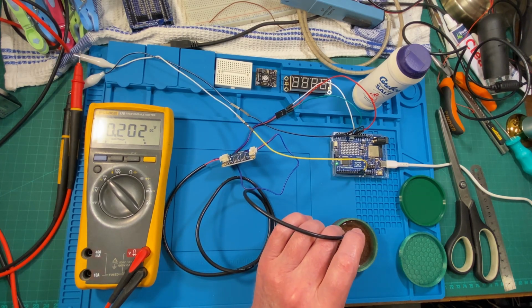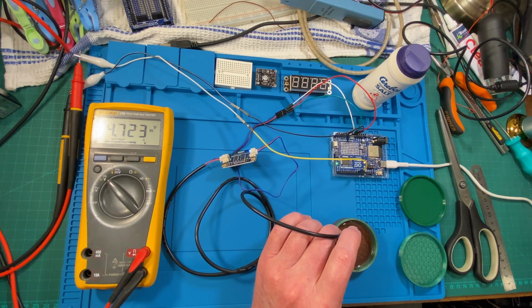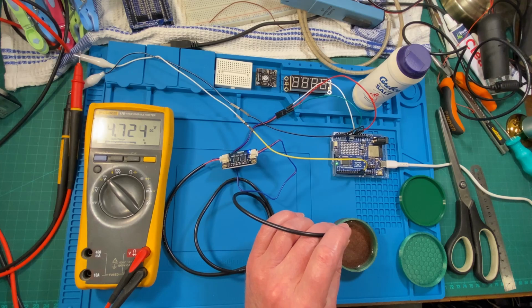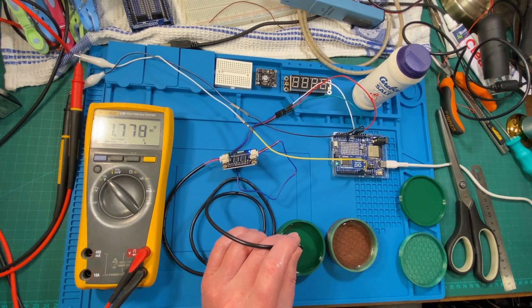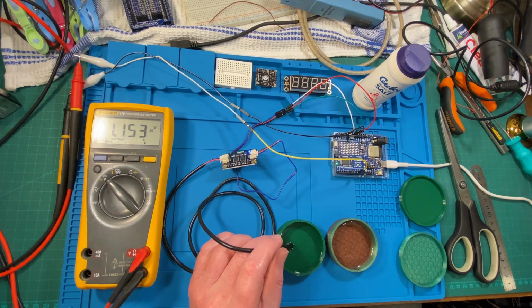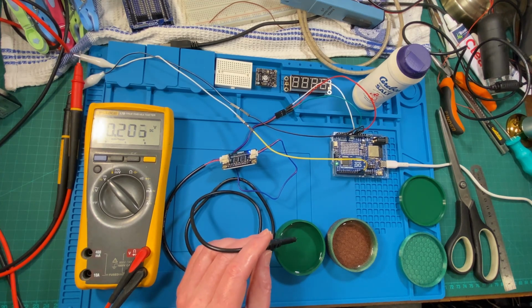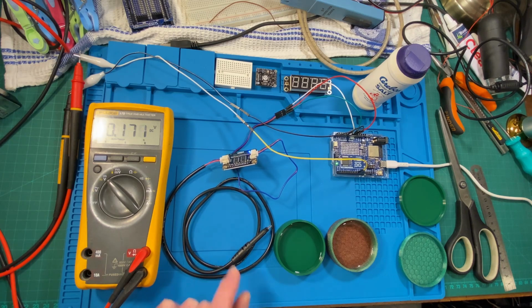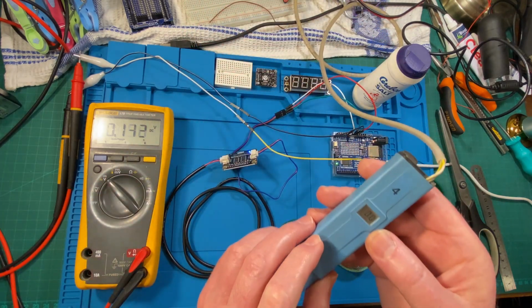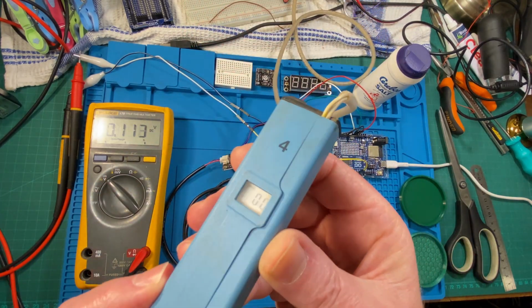When I take this and dip it into the water with the sodium chloride, it goes off scale. And then back into our tap water, like so. There you can see the analog value out, and also on the computer, or confuser as I like to call it, we can see the value being transmitted over serial comms. So let's power up the commercial probe. That's reading 0 at the moment.